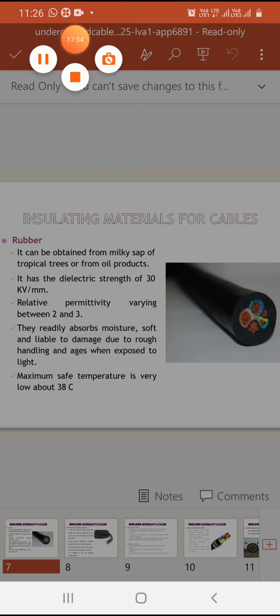Now the next insulating material is vulcanized rubber. Vulcanized Indian rubber is nothing but VIR, which is prepared by mixing pure rubber with mineral matter such as zinc oxide, red lead, etc., and 3 to 5% of sulfur. This compound so formed is rolled into thin sheets and cut into strips. The rubber compound is then applied to the conductor and heated to a temperature of about 150 degrees centigrade. This process is called vulcanization, and the product obtained is known as vulcanized Indian rubber.